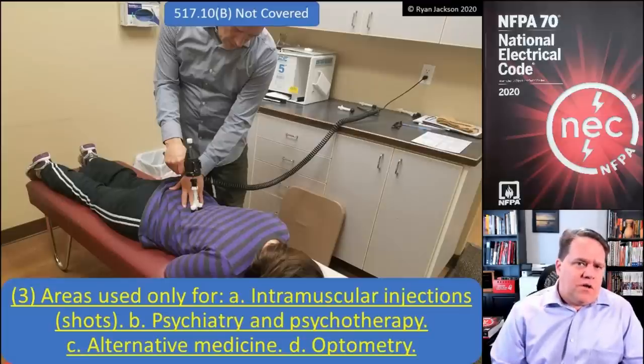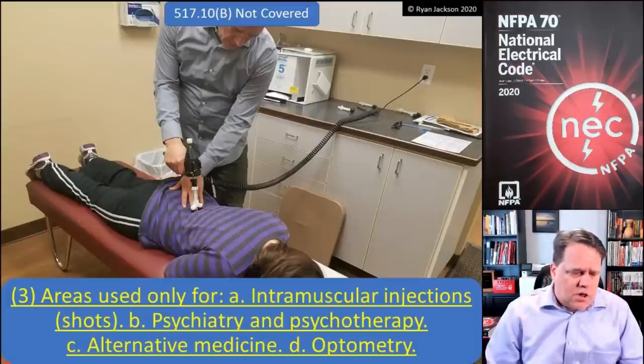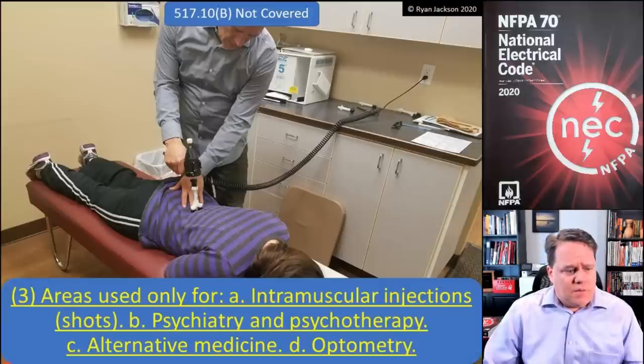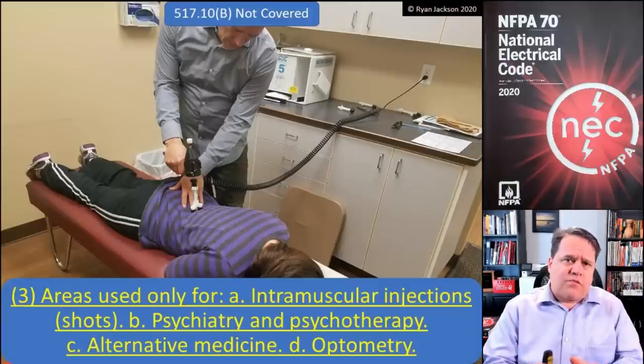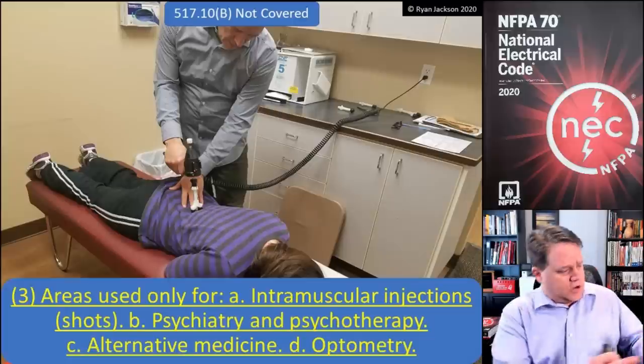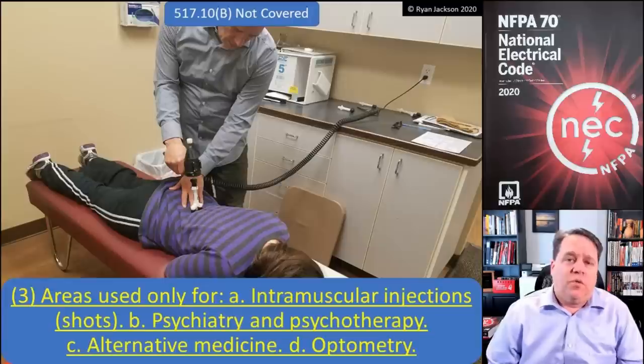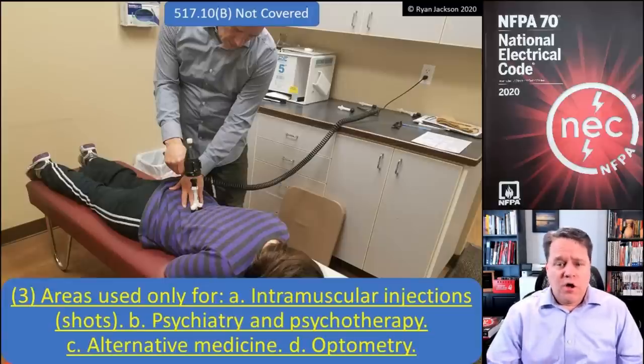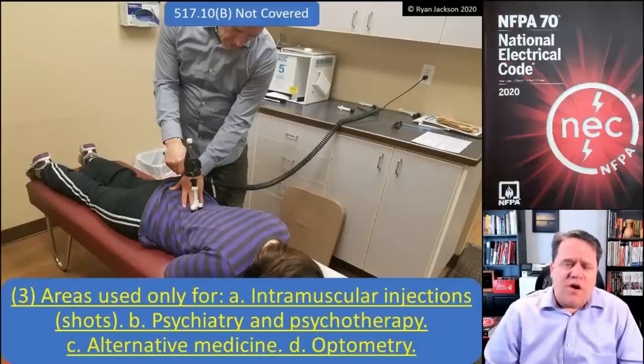Item C covers alternative medicine. You could argue that chiropractic, acupuncture, or acupressure may or may not be healthcare. This just removes the discussion — if you want to call it healthcare, fine, but this section says we don't have to follow Part Two of article 517. So a chiropractor's office would not need to be wired with any special wiring methods.